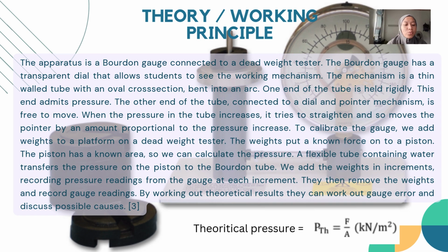to the pressure increase. To calibrate the gauge, we add weight to a platform on a dead weight tester. The weight puts a known force on the piston. The piston has a known area, so we can calculate the pressure. A flexible tube containing water transfers the pressure on the piston to the Bourdon tube. We add the weight in increments, recording pressure readings from the gauge at each increment. Then we remove the weight and record gauge readings. By working out theoretical results, we can work out gauge error and discuss possible causes.